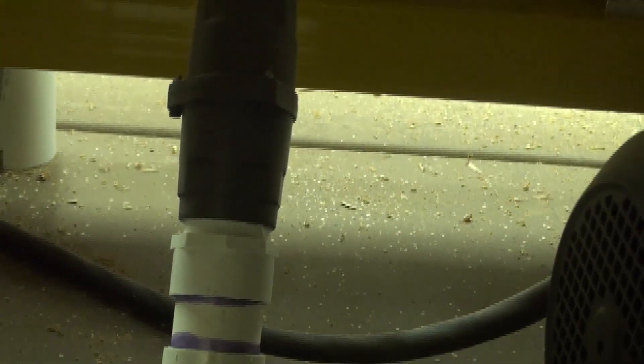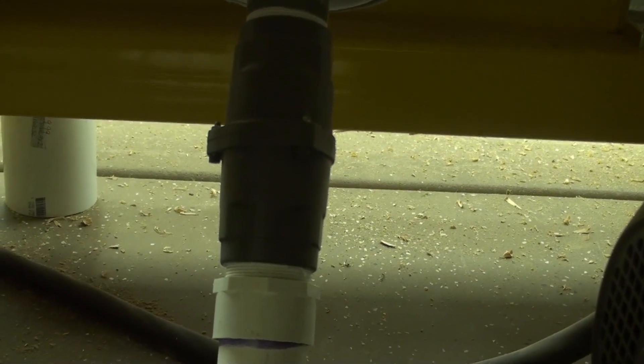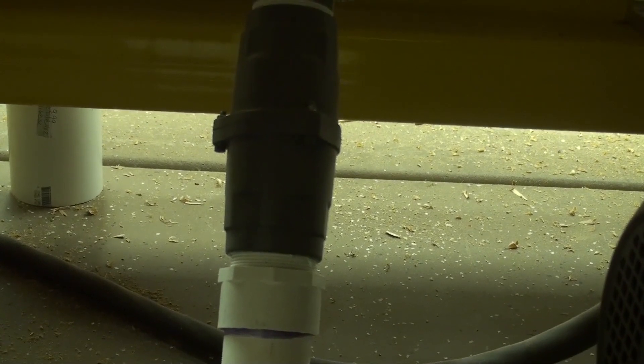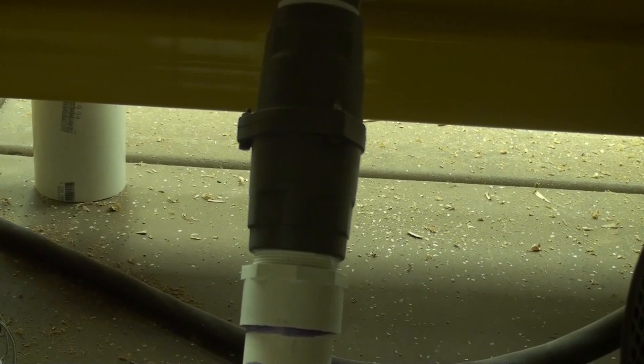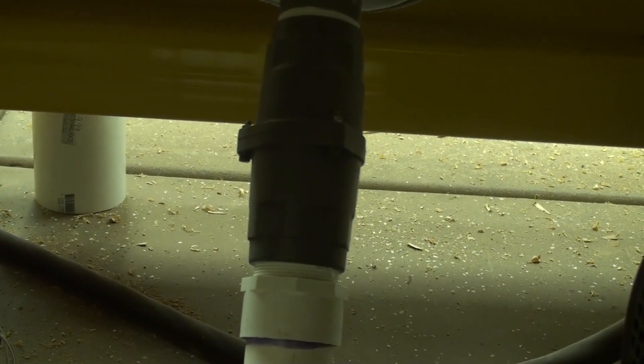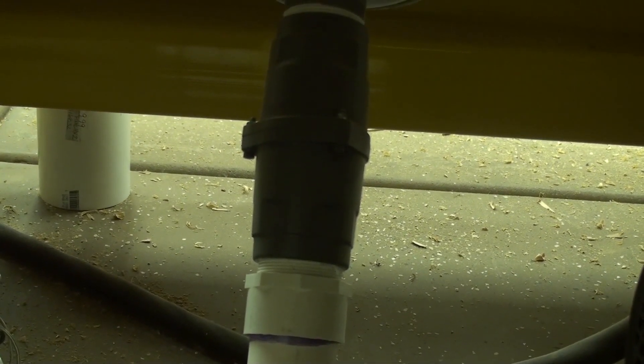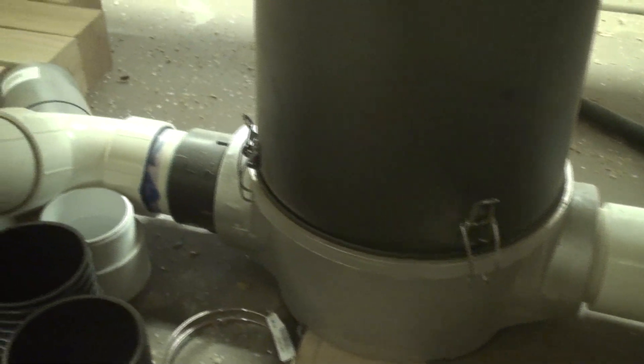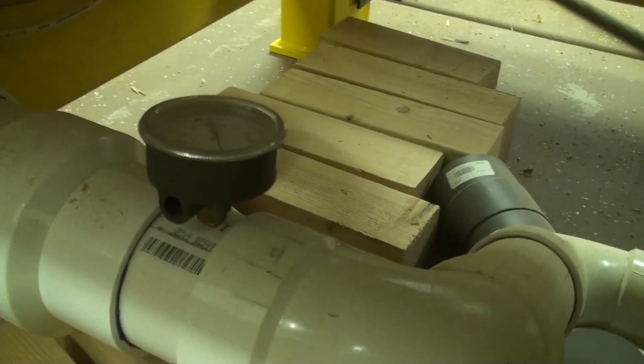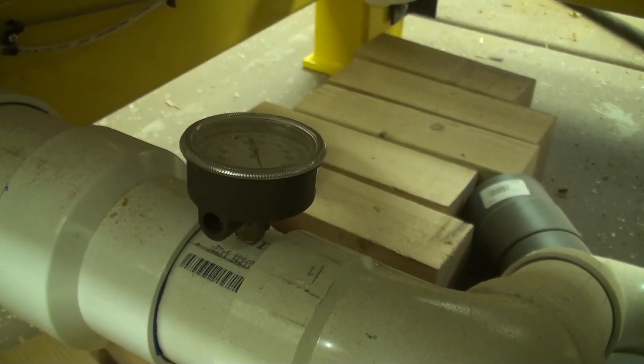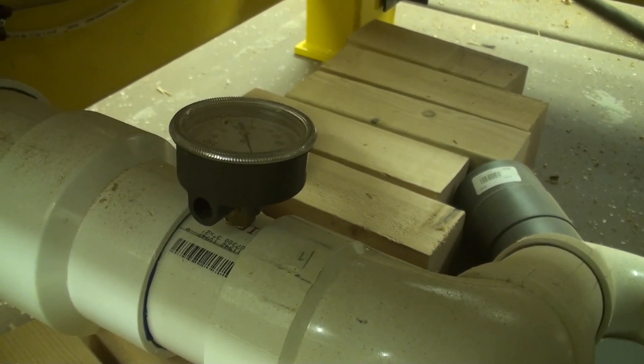Then we have our valve, our pop-up valve and be sure you follow the sticker on the valve of direction of flow. And that's so when the machine is sucking so many pounds of vacuum, this is a relief valve because it can't just continue to suck and suck and suck, so at some point it has to have a relief. This opens up and allows more air to come in so that you don't ruin your pump. And then of course because it's an inlet of sorts you have to have a filter on it. So then you keep coming down the pipe and then you've got your big huge canister filter here. And then you keep coming down the pipe like this and it goes into your table. And then you've got your vacuum pressure gauge screwed in inline there on the pipe so that you can see how much vacuum the pump is pulling.